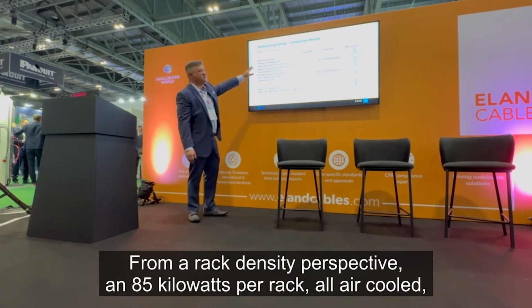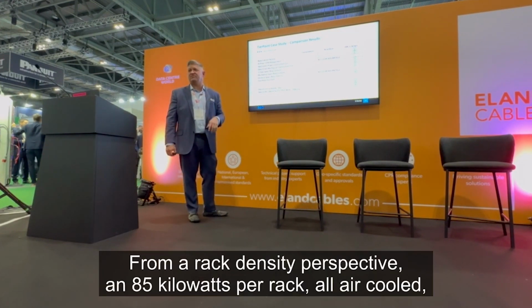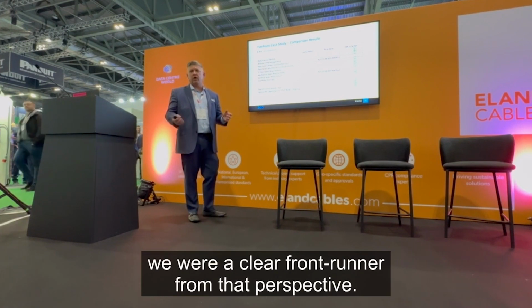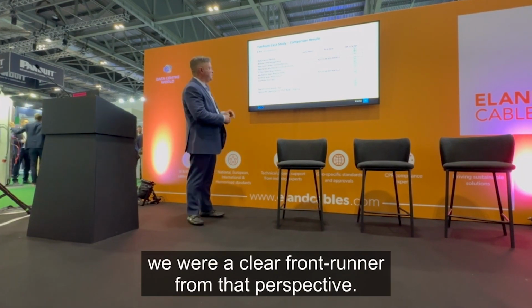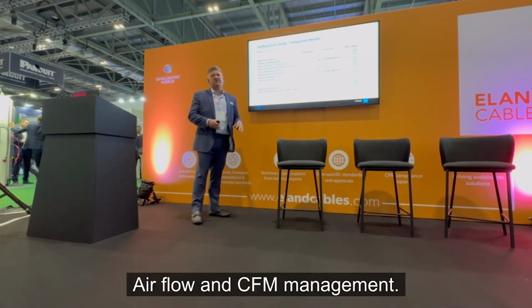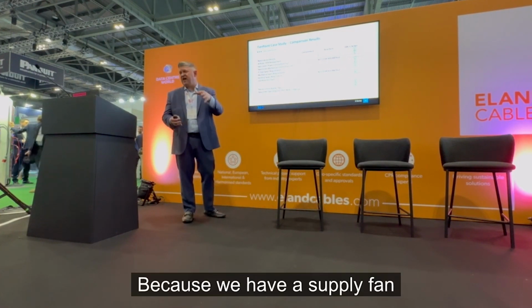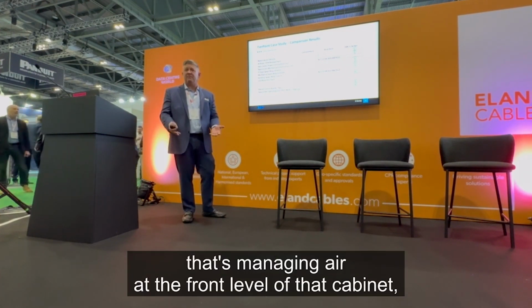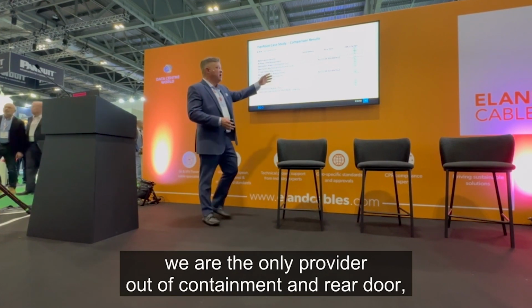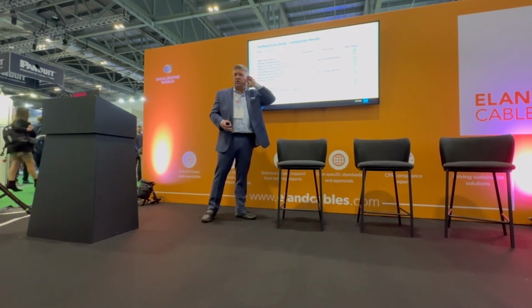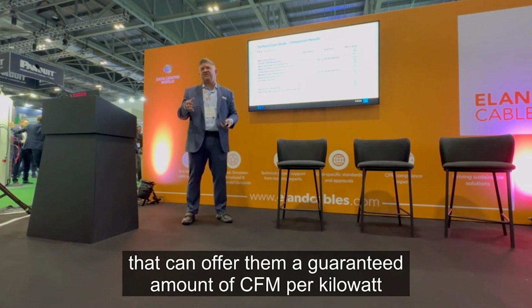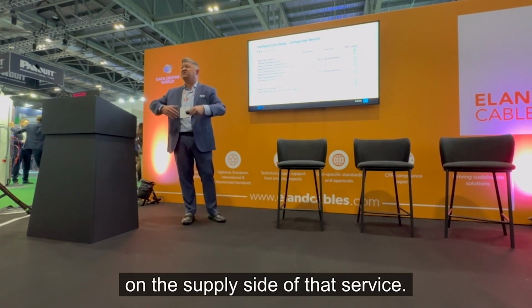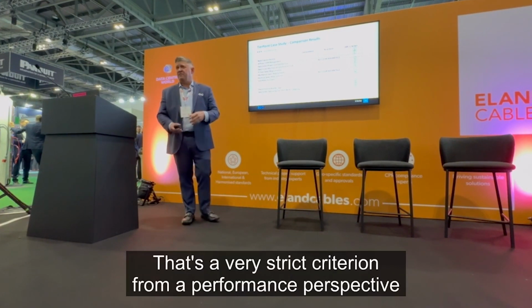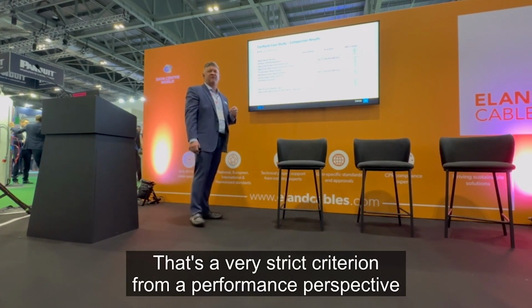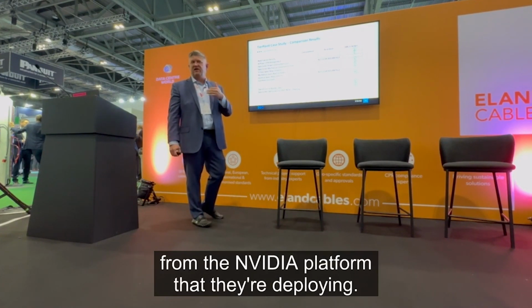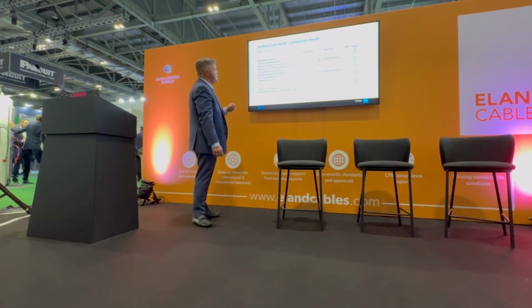From a rack density perspective, at 85 kilowatts per rack, all air cooled, we were a clear front runner. For airflow and CFM management, because we have a supply fan managing air at the front of the cabinet, we were the only provider out of containment and rear door options that could offer a guaranteed amount of CFM per kilowatt on the supply side of the server. That's a very strict criteria from a performance perspective for the NVIDIA platform they're deploying.